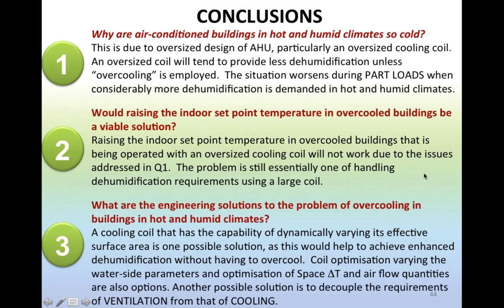Would raising the indoor set point temperature in overcooled buildings be a viable solution? Well, the answer is no. Raising the set point temperature alone is not a solution because we have issues related to dehumidification, which is basically question one that I highlighted just now. The problem is still essentially one of handling the latent loads, the dehumidification requirements from a large coil.